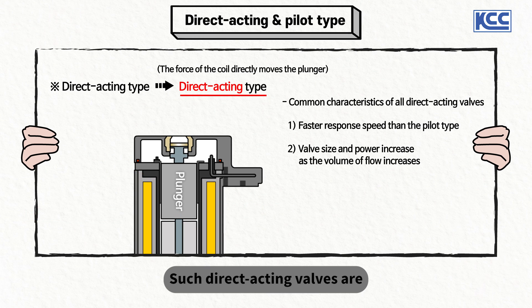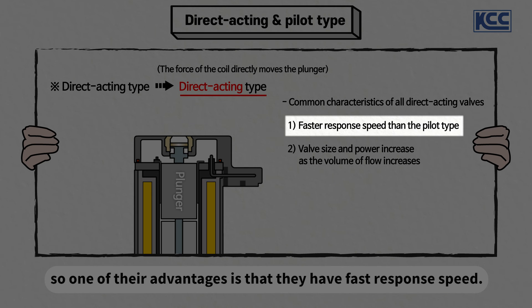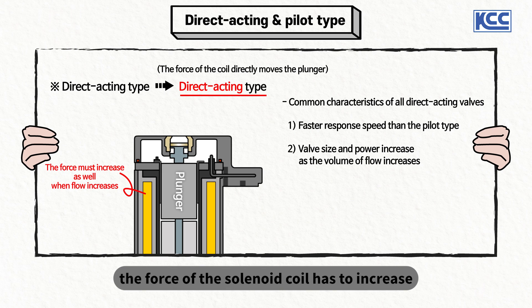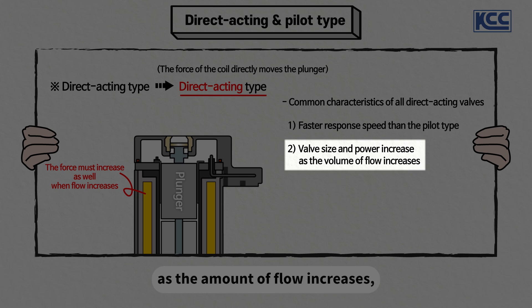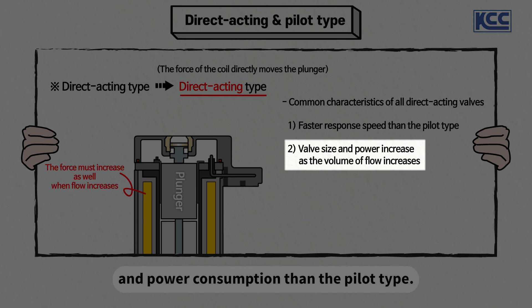Direct acting valves are operated directly by the force of solenoid coils, so one of their advantages is fast response speed. Since this type of valve is operated only by the force of a solenoid coil, the force of the coil has to increase as the amount of flow increases. This may require a relatively larger size of valve and higher power consumption than the pilot type.